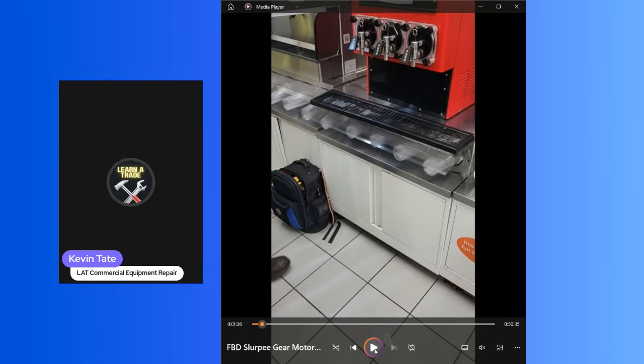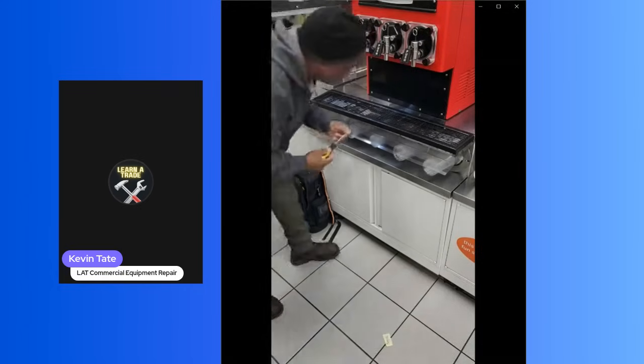As you can see on this one, it has a compressor ran too long error, and a lot of times that can be a number of different issues. That could be a brix issue, a beater motor issue, a refrigeration issue, or it could have a low charge on the system. In this case, it was the beater motor issue, so we'll go from there.